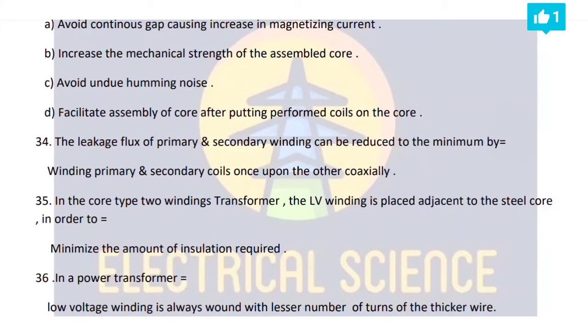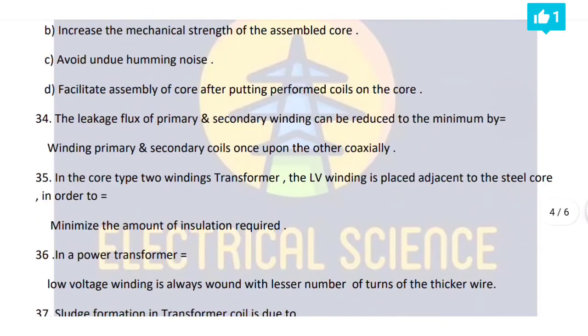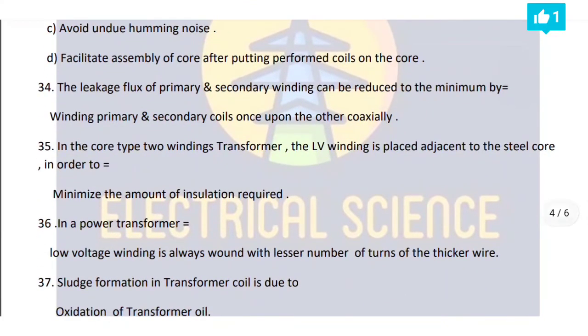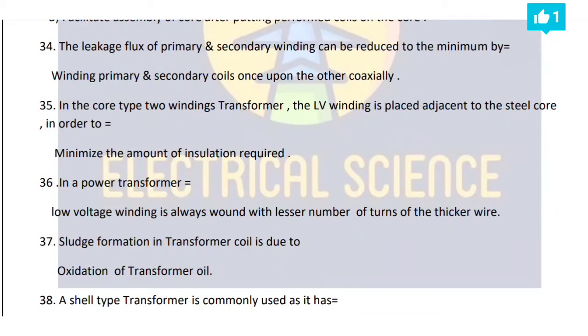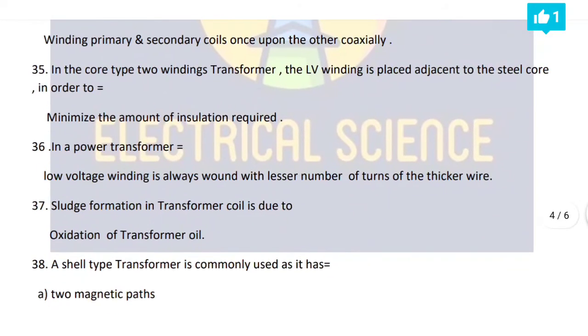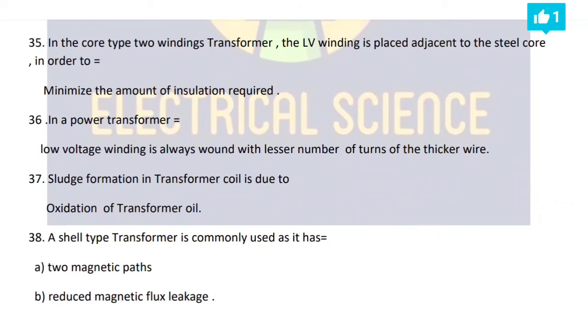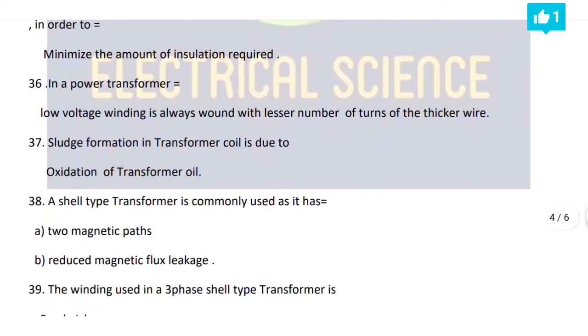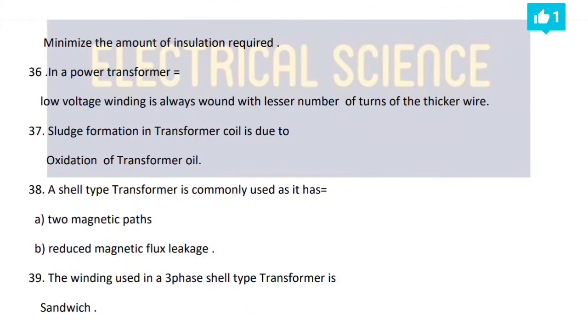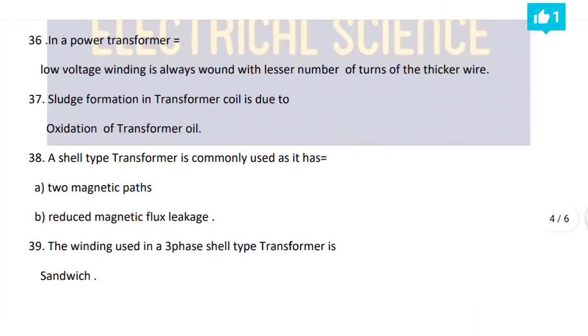34th point, the leakage flux of the primary and secondary winding can be reduced to a minimum by winding the primary and secondary coils one upon the other coaxially. 35th point, in the core type two winding transformer, the LV winding is placed adjacent to the steel core in order to minimize the amount of insulation required. 36th point, in a power transformer, the low voltage winding is always wound with a lesser number of turns of thicker wire. 37th point, sludge formation in a transformer coil is due to oxidation of transformer oil.